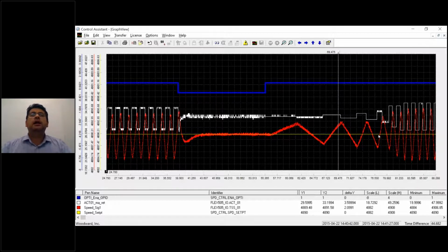In this application, the customer has used the adaptive PID tuning a couple of times, so he was able to achieve a very nice performance out of his turbine. And this is where we did the first adaptive PID tuning and we start to see the behavior changes. I'm going to zoom in so that you can see what we actually do with the adaptive PID tuning.